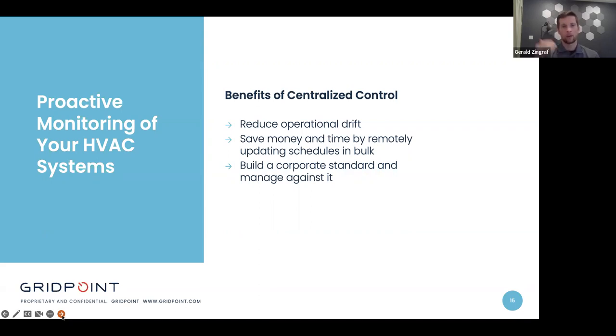So you've decided that, okay, we're going to drop the set points by a degree for this heat wave. The heat wave is going to be a week and a half, because we want to really limit our hot-cold calls coming in. So you make that adjustment across 60 sites, and it takes a few clicks if you have centralized control. And when that week and a half is up and the heat wave is gone, you can come back into the system and adjust it back to the baseline, back to your corporate standard, with a few clicks. If you don't have centralized control, this requires a lot of emails, a lot of follow-ups, a lot of trust and faith in the SOPs and the managers that are actually on site. So a lot of benefits from centralized control by bringing it all in-house in one place.